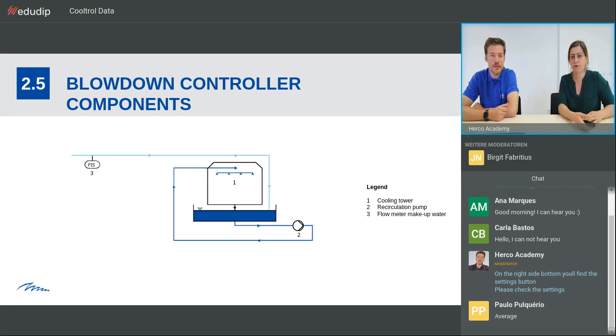As we have evaporation and drift, so water losses in an open circuit system, we need makeup water, which is shown here in light blue. The makeup water line has a flow meter usually, shown with the number 3 here. And the makeup water is of course regulated for the level of water in the cooling tower basin.